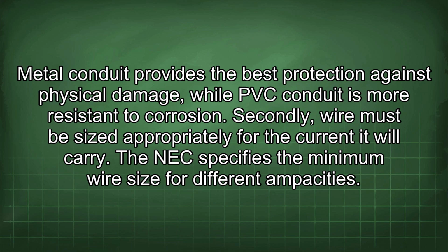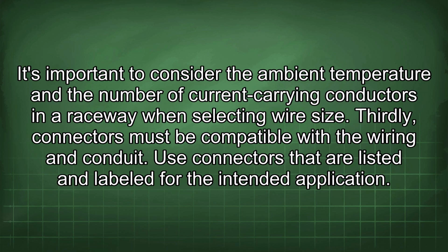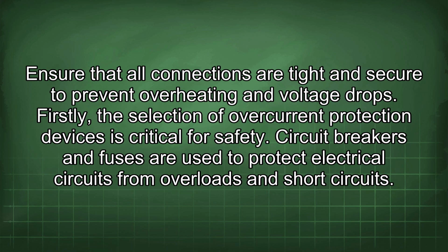Secondly, wire must be sized appropriately for the current it will carry. The NEC specifies the minimum wire size for different ampacities. It's important to consider the ambient temperature and the number of current-carrying conductors in a raceway when selecting wire size. Thirdly, connectors must be compatible with the wiring and conduit. Use connectors that are listed and labeled for the intended application. Ensure that all connections are tight and secure to prevent overheating and voltage drops.